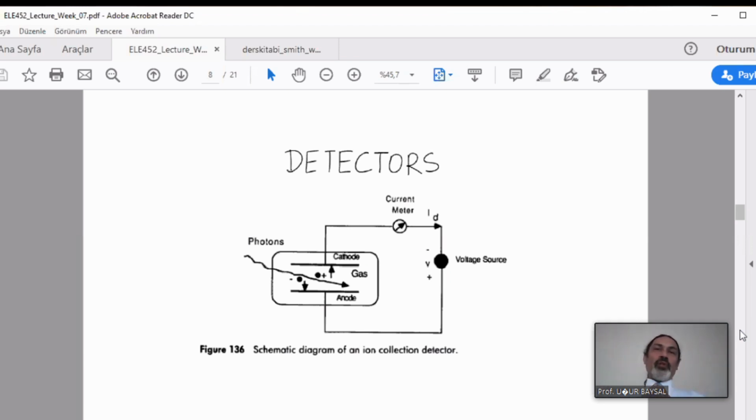The patient lies on a table, and there are detectors around the patient because there's no gamma ray radiation source inside the instrument. The only gamma ray source is the patient itself. So in that nuclear imaging department, people running around are actually sources of gamma rays. They are emitting rays, so they have to wait in a special room, shielded with lead or other material, not to harm other divisions of the hospital.